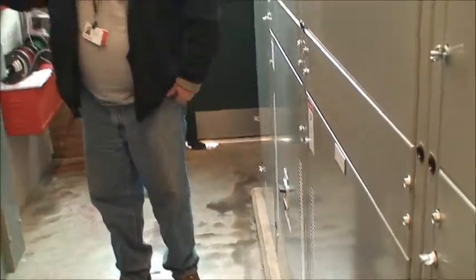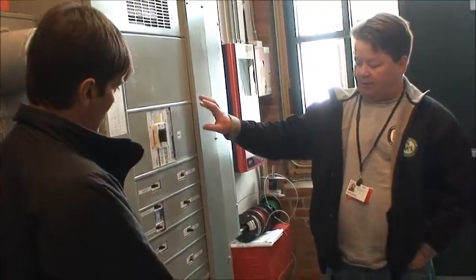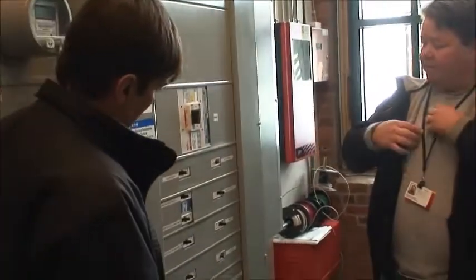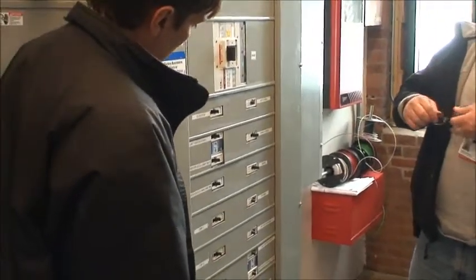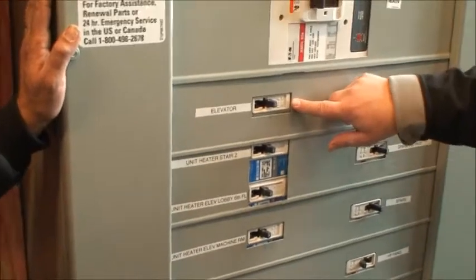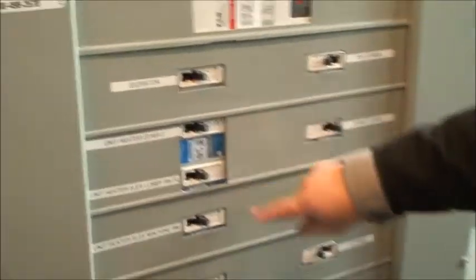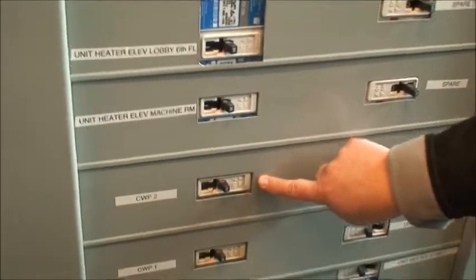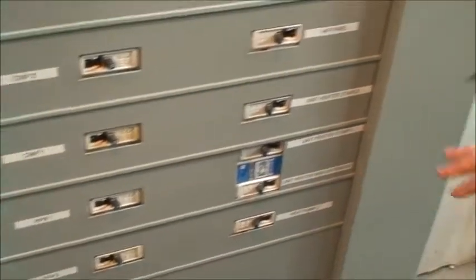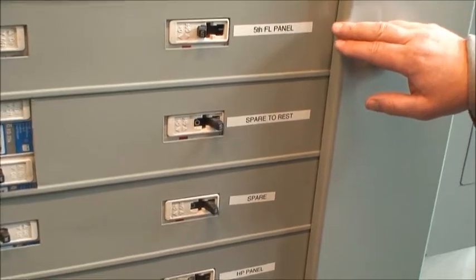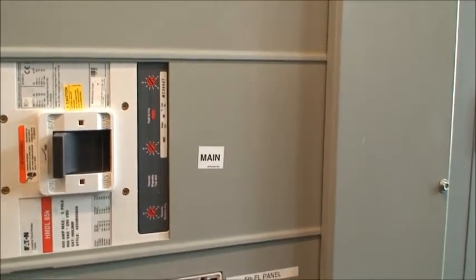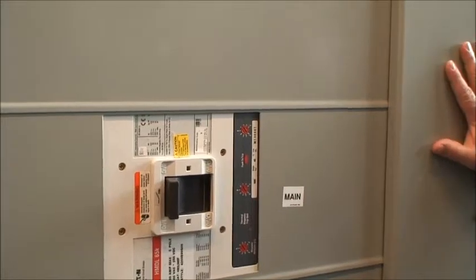This is bussed over, and behind here there are connections by N-Star, which allow us to meter this. You have a connection from this 800 amp breaker to this main underground, like I said. Then everything that's picked up off of your public is all marked here. Your different panels, you have your elevator breaker, unit heaters, chilled water pumps, hot water pumps, everything marked, everything you'd have for the public, your panels, 5th floor panels. So it's pretty self-explanatory on that end, for that's your public panel.